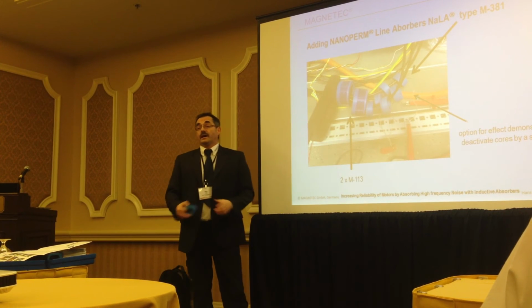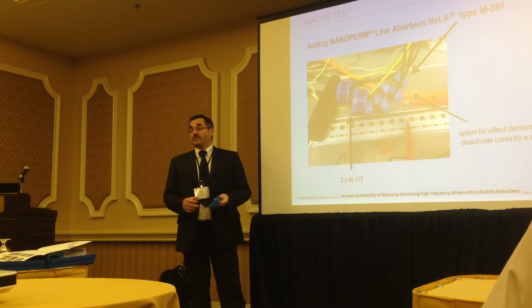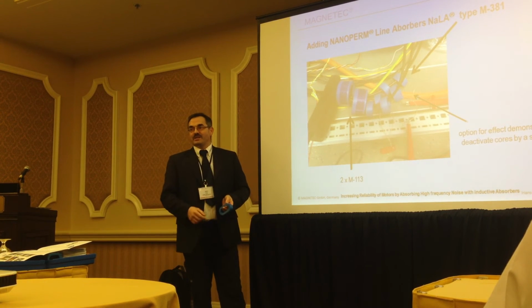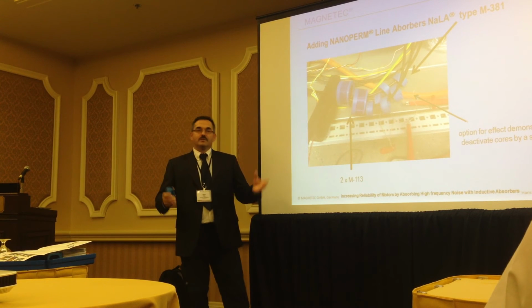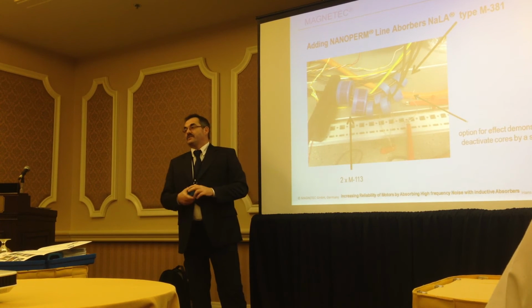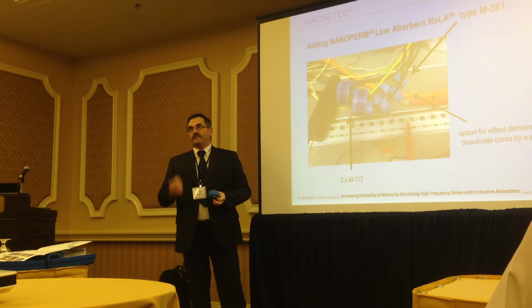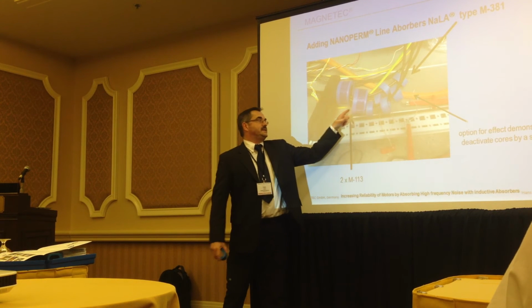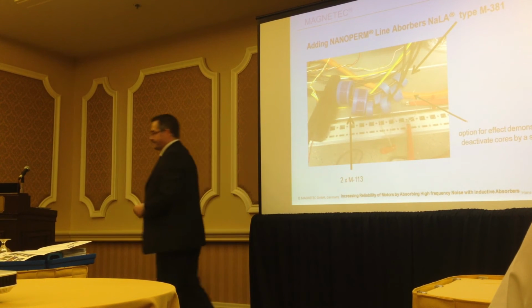Especially when you're working in the higher power range, you have the problem that the cables are a little bit thicker than my thumb. So imagine having to open the cables, mount the cores, and then demount them again. That can last - I worked on a 6 megawatt drive, I would say 1.5 days. So with this small trick, you can easily judge how many cores you need.